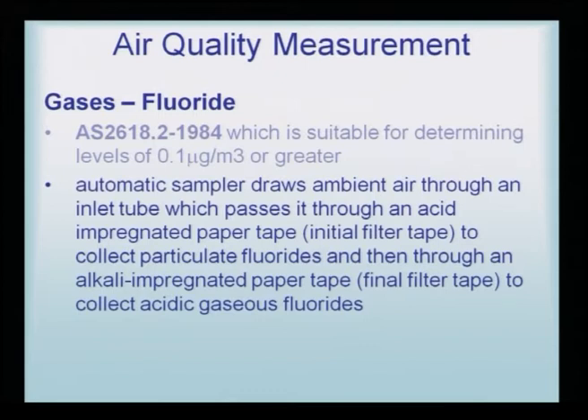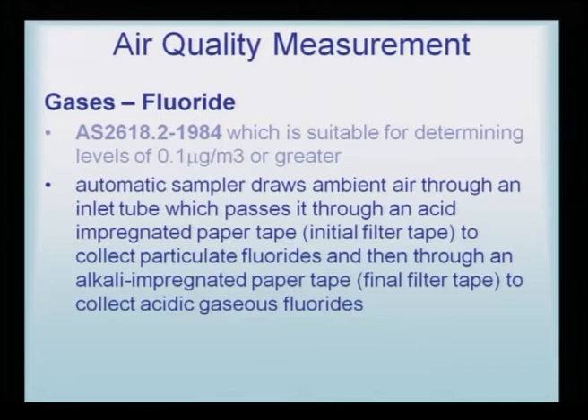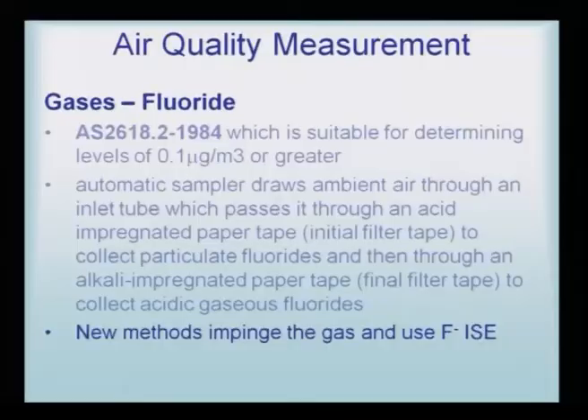An automated sampler draws ambient air through an inlet tube, passing it through an acid-impregnated paper tape — an initial filter tape to collect particulate fluorides — and then through an alkali-impregnated paper tape — a final filter tape to collect acidic gaseous fluoride. These two types of filter tapes are impregnated with different fluoride species and total gaseous fluoride is then evaluated. A newer method impinges the gas and uses a fluoride detector called F- ISE.